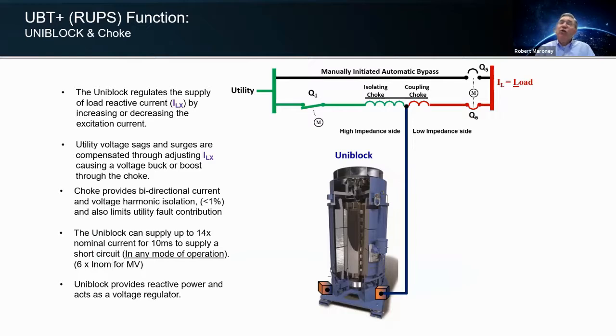So let's start to build a UPS with this system. As you look at the top here, you can see we have our input and output, utility and load. We have a manually initiated automatic bypass, and then we have the Q1 input breaker, and we talked about our choke. So we have our isolating choke, which is the high impedance choke, and then our coupling choke, which is our lower impedance choke, which allows us to provide isolation input to output.